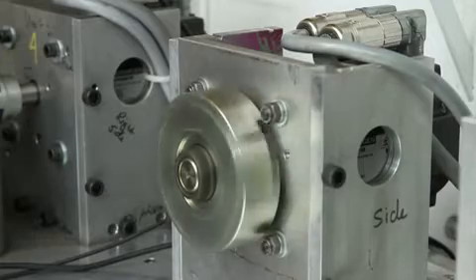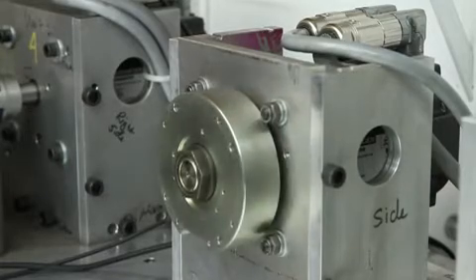If you're on a pick-and-place robotic machine and you need to move at 15 to 20,000 rpm, that is an absolute application for a servo system. However, if you're a hole-punching machine or you're a banding machine or a packaging machine and most of the time you're in that 500 rpm or 750 rpm range, a wrap spring is a more elegant solution.